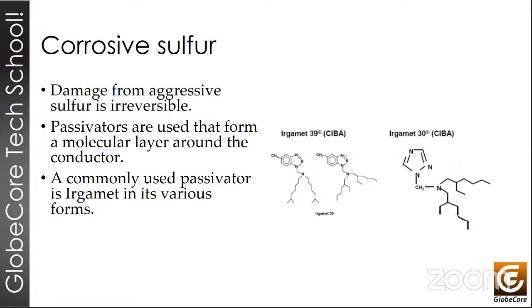The problems arising from corrosive sulfur are irreversible. So once a part of the transformer suffers corrosion damage, it cannot be repaired. But the chemicals that we add usually need to be dosed into the oil with much care, because uncontrolled increase of these chemicals can also be detrimental to the transformer. A good time to add them is when you're doing a thermal vacuum purification, for example, because you can precisely dose the required amount of this chemical into the oil at this point.